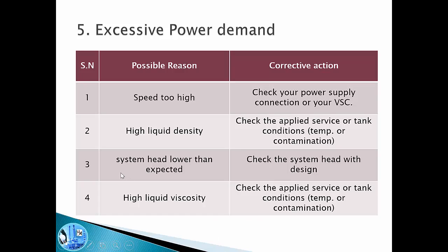A third possible reason for excessive power demand is system head lower than expected. If the pump is working against very low resistance from the system, it will deliver more flow and consume more power. We need to verify the pump is working against the design system head it was intended for. It could also be high liquid viscosity due to low tank temperature or contamination from another liquid making the fluid more viscous, causing the pump to consume more power than the design value.